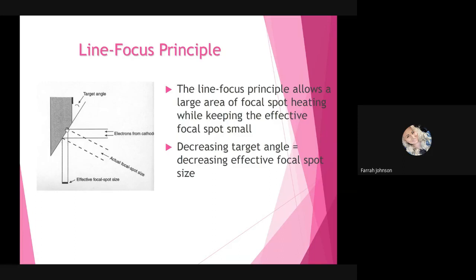Now, the area that they interact with on that target angle is going to be considered your actual focal spot size. Okay, it is that area in which these electrons are going to interact. Now, after interaction, when they get emitted out of your X-ray tube, that is what you call your effective focal spot size. And when you decrease this target angle, you are going to decrease your effective focal spot size. Okay, now note that a small focal spot is going to give you greater detail. So a small effective focal spot is ideal.